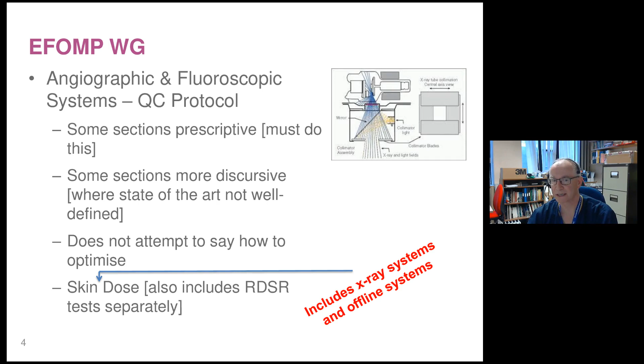So I want to just say how we in the working group are approaching the difference between acceptance testing and commissioning for general testing. And I'm going to talk specifically here about skin dose modeling. So our view is that an acceptance test is a test designed to show that the results you get are as specified by the manufacturer. So if it was a simple dose check, you'd want to know that the dose was in specification.